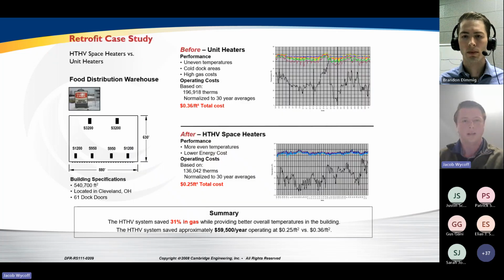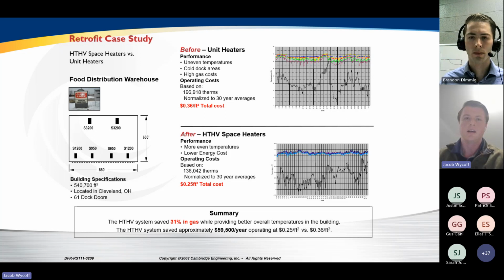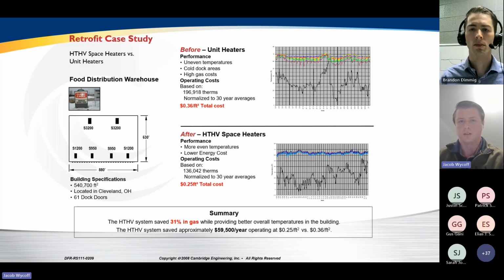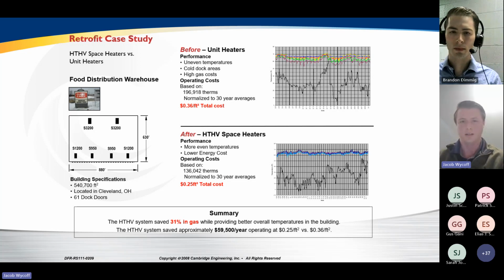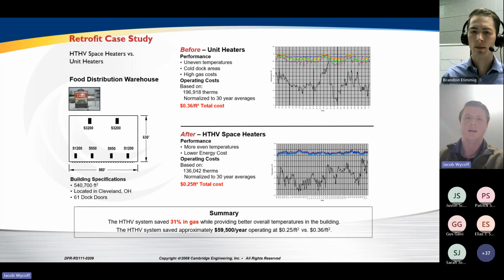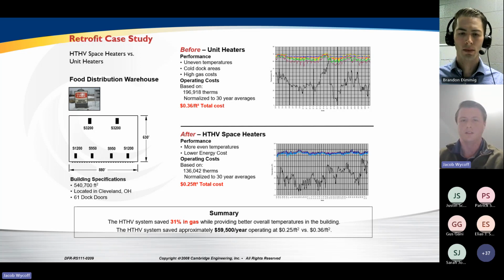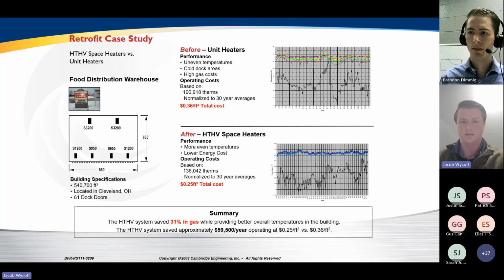So here's an example of a building in Cleveland, Ohio, roughly 540,000 square feet with 61 dock doors. Before, they had a unit heater design, and they were having a lot of issues with uneven temperatures, with cold dock areas, and they thought their gas bills were a little bit high. They came in and replaced those unit heaters with HTHV space heaters. They were able to achieve more even temperatures and they were able to save energy.